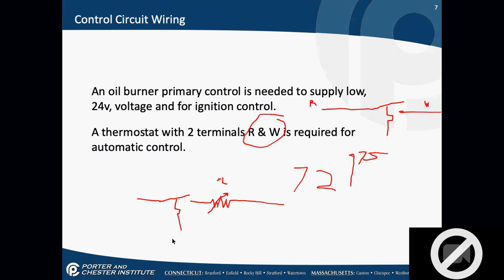Okay? It is one of the few control devices that we put in series. Remember I said 90% of the time, 99% of the time, we don't have 2 loads in series. But that heating anticipator is one of the few control devices I might put in series with another device. It's built into the thermostat. It is not in digital thermostats. Okay, it is only in the old Mercury thermostats. By the way, when I put a dotted line around something, it means it's one device. Okay, 9 out of 10 times you do not even need to think about this being there, but it is there.